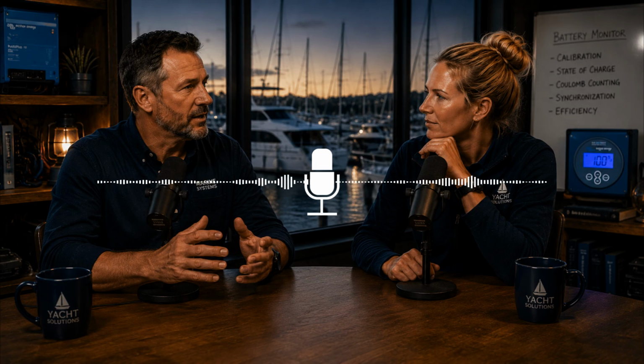Hardware, not software. Exactly. The Victron monitor relies entirely on a physical block of metal called a shunt to measure the current. The rule for wiring a shunt is absolute and unforgiving. What's the rule? All electrical loads and all charge sources must be connected to the system side of that shunt. Nothing gets to skip the line. Nothing. The only thing connected to the battery-only side of the shunt should be the main negative cable coming directly off the battery terminal. So if a solar controller or an inverter bypasses the shunt and wires directly to the battery, the monitor simply cannot see those drops of water entering or leaving the bucket. It goes completely blind to that energy.